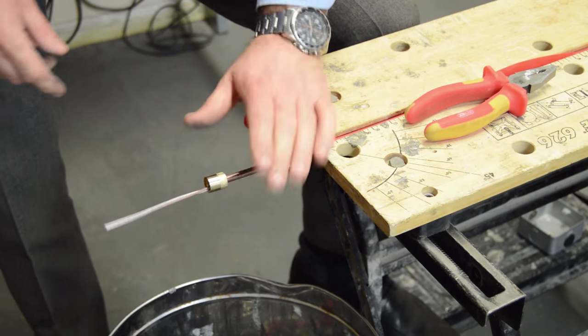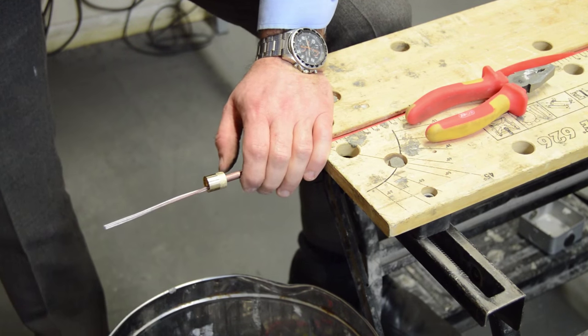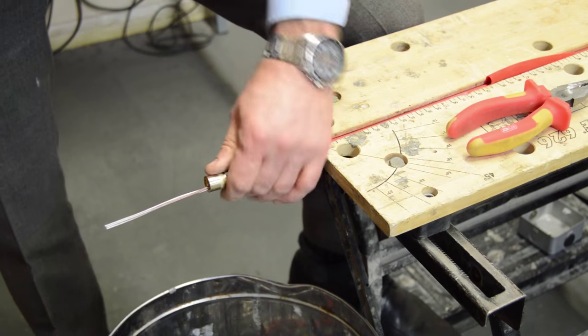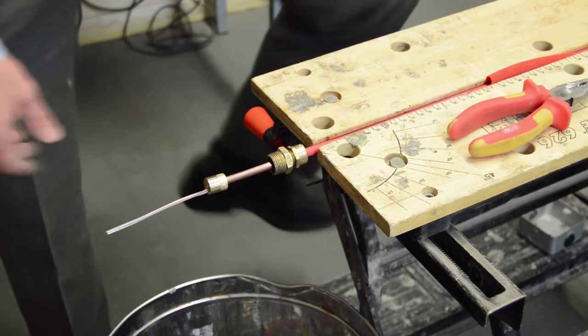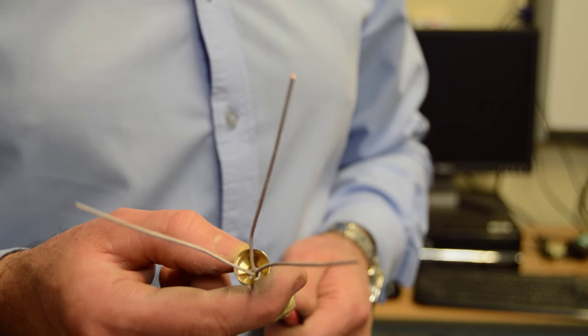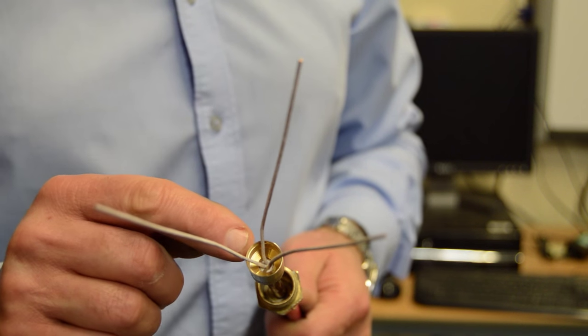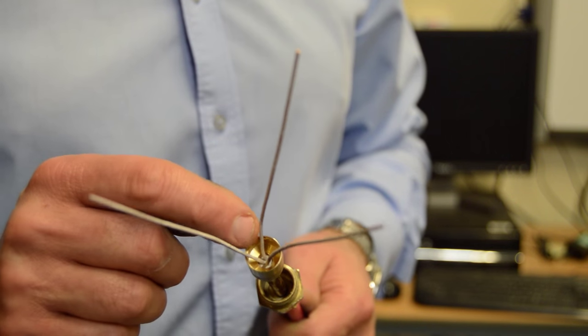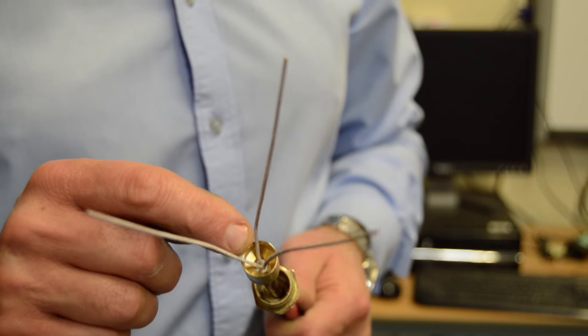One important part, make sure you don't blow into the magnesium oxide because the magnesium oxide is hygroscopic and will absorb the moisture out of your breath and could result in a short pot. So what I suggest you do, just tap your pot out, don't blow on it. As you can see now we've wound the pot on so far that the outer sheath, the copper cable, extends into the inside of the pot. Now it has to be below the dome by about one or two millimeters, so about that distance there.